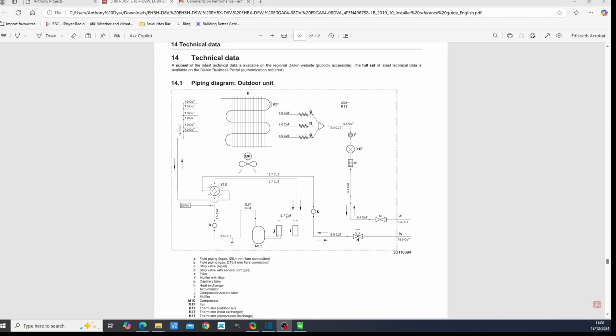So I think we need to go to this piping diagram to understand what's going on. So in the inefficient case, what I think we're seeing is this compressor running all the time. We're seeing 320 watts with occasional peaks at 415 watts. You've got this fan unit here, you've got this compressor unit here, and when they're both running together, you will have a minimum flow going through here, and then you have a heat exchanger here. So you have compressed gas going through here, and not all of the heat is being transferred to the heating medium, the water. The consequence is that when it comes back to your evaporator coil, you don't just have liquid, you also have gas as well. So you don't have a full phase change going on from gas to liquid.